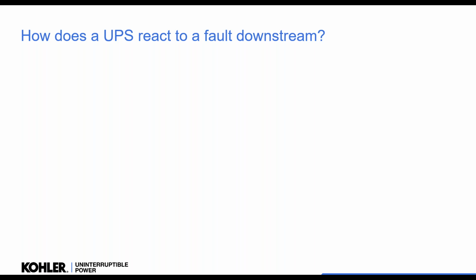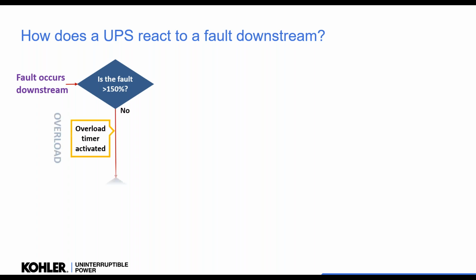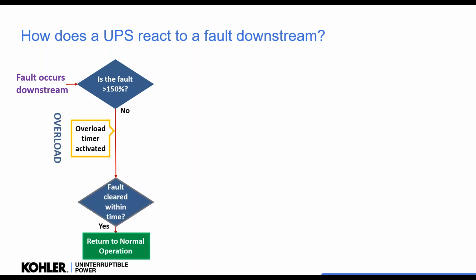So how does the UPS decide what to do? This is quite generic for different UPSs. Firstly, it decides if it's over or under 150%. Most UPSs can run up to 150% as an overload, which means it's going to maintain output voltage. Above 150%, it has to protect itself and current limit, which we would class as a short circuit. So if the fault is under 150%, then we will use the overload capability to trip the distribution device if possible. And if it does, great, everything returns to normal, comes out of overload.